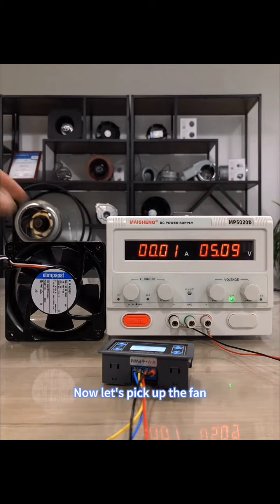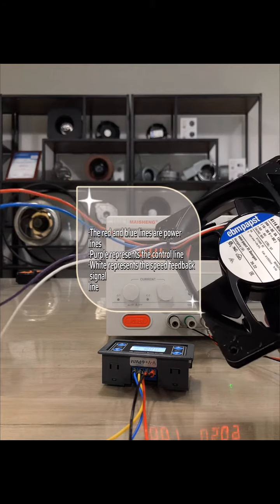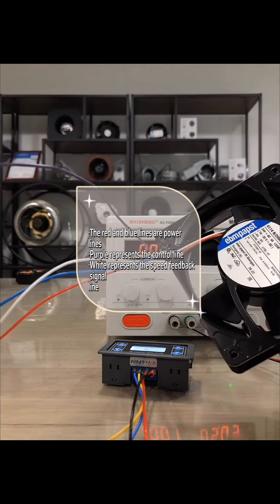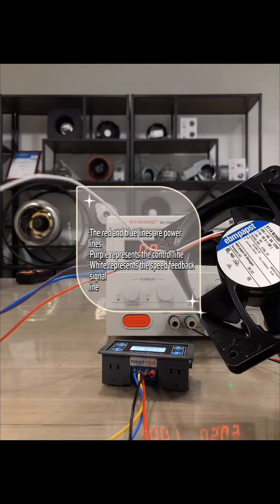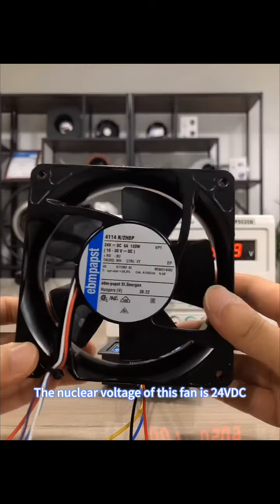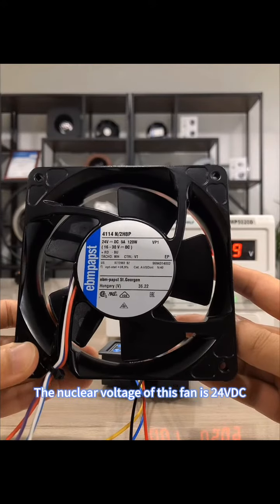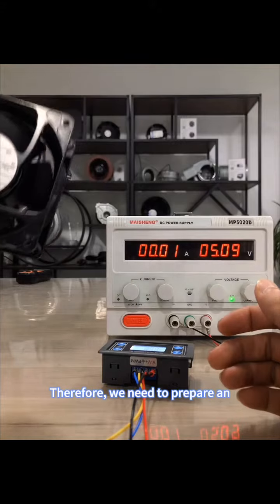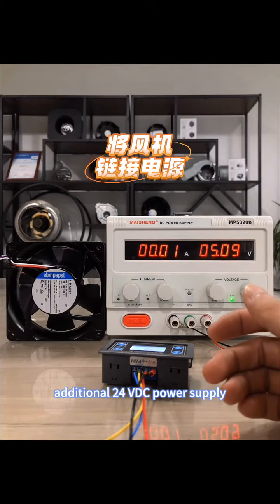Now let's pick up the fan. The red and blue lines are the power lines for the fan. The purple line is the control line of the fan. White is the speed feedback signal line. The rated voltage of this fan is 24 volt direct current. Therefore, we need to prepare an additional 24 volt direct current power supply.